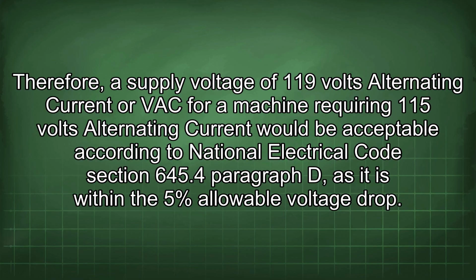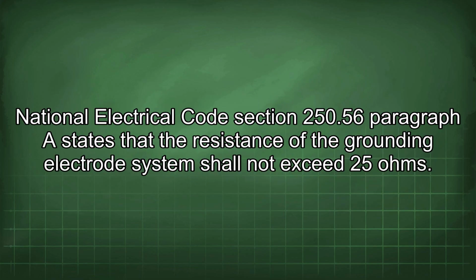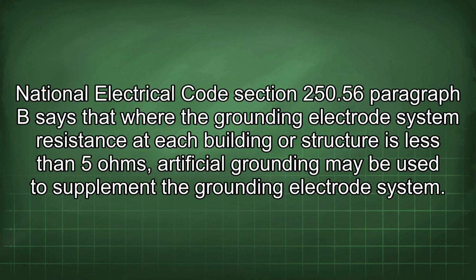National Electrical Code Section 250.56 paragraph A states that the resistance of the grounding electrode system shall not exceed 25 ohms. National Electrical Code Section 250.56 paragraph B says that where the grounding electrode system resistance at each building or structure is less than 5 ohms, artificial grounding may be used to supplement the grounding electrode system.